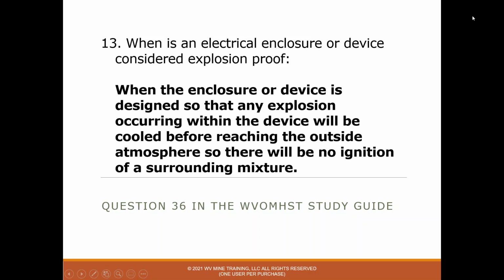So we just talked about that. We have 0.004 of an inch gap. That's the maximum size we can have to make this an explosion proof enclosure. Again, it will not cause an explosion. If you do have an explosion within the device, it will be cooled before reaching the outside, so there can be no ignition of a surrounding mixture. Someone told me they asked that on the test. They kind of reversed that. They kind of want to know the definition of an explosion-proof enclosure, so make sure you understand that both ways. Either way, they could ask it.